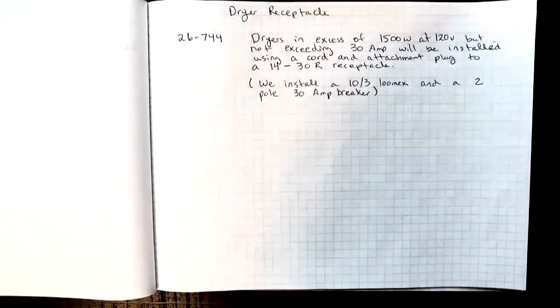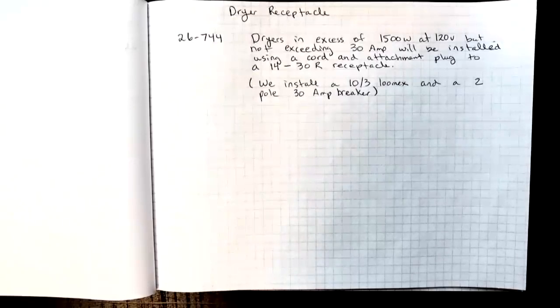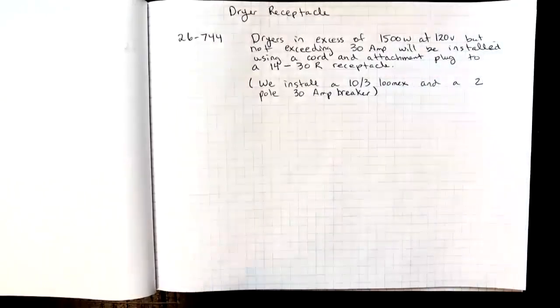The dryer in excess of 1500 watts at 120 volts but not exceeding 30 amps will be installed using a cord and attachment plug and a 14-30R receptacle. We install a 10/3 Loomex and a 2-pole 30 amp breaker to feed this dryer.